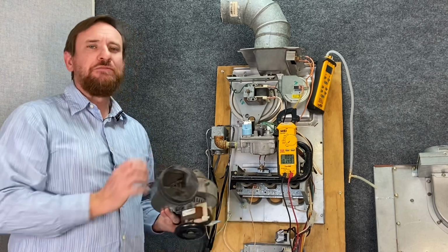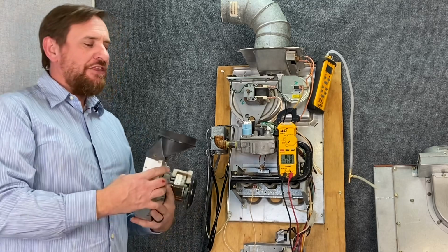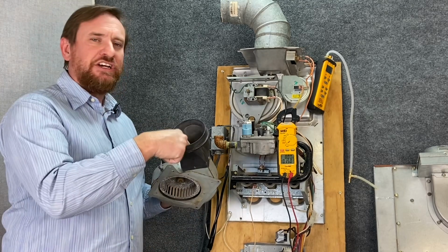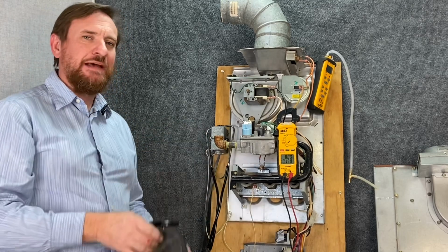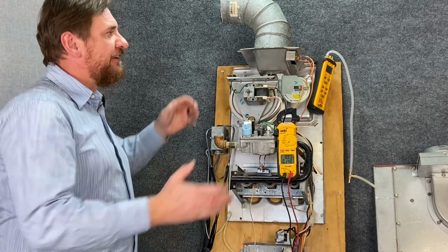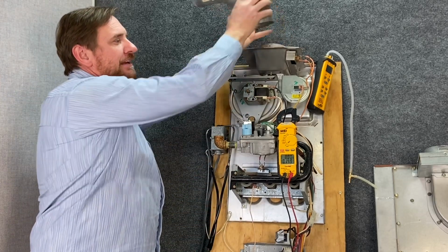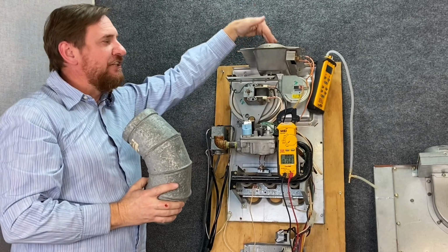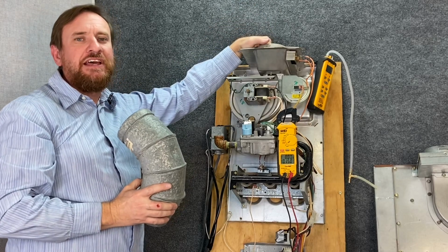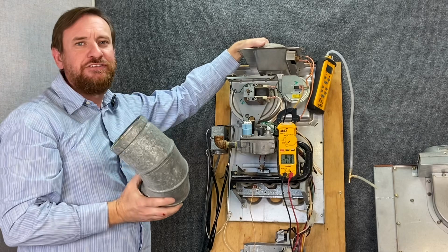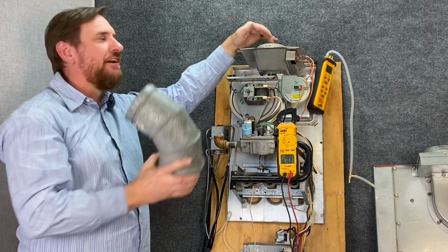So instead of pulling this motor off and checking it every time, there's a simpler method. We can actually look in the very end and we can see what's happening with the blade. If we're working on a furnace, I would take this vent pipe entirely off, take my flashlight, look down inside of here, or even better yet, I could use an endoscope that attaches to your phone and you can get a better view of what it looks like.